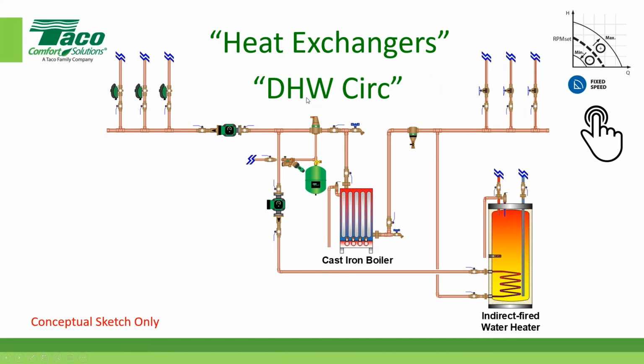Anyway, we're looking at a heat exchanger and a domestic hot water circulator over here. Now, I want to point a couple things out. First thing is, if I'm still talking about fixed speed over here, do I put a check mark by that, knowing that I have feedback capable to give this circulator the ability to automatically speed up or slow down? And of course, I'm going to put a red X by that. If I'm still talking about fixed speed, I'm focusing on this pump, right? Notice all I want to do is get that coil hot, and I want to get it hot as quickly as I can. So I might adjust the speed of this to the GPM required to give me the recovery that I want on this particular tank. So you see why fixed speed is still an appropriate mode for an indirect fired water heater application. There's nothing within this loop that's going to give this pump the feedback it would need in order to ramp itself up or down.